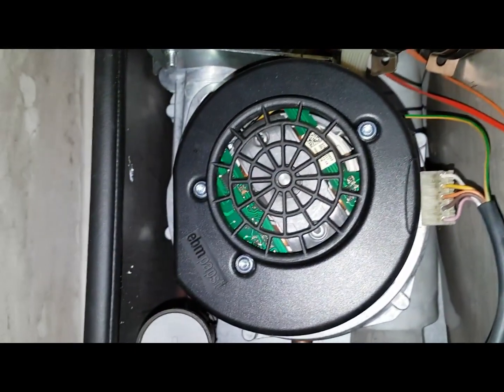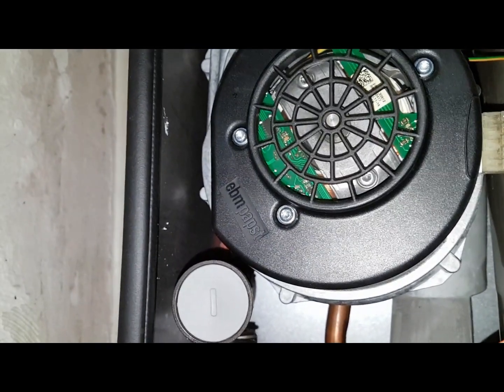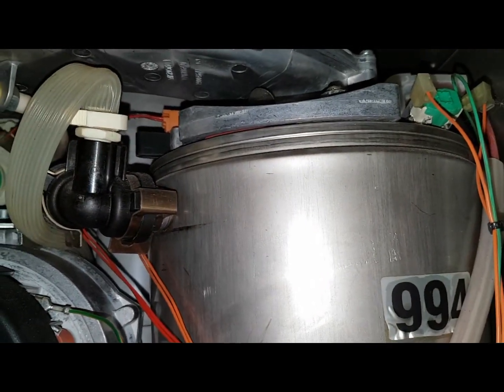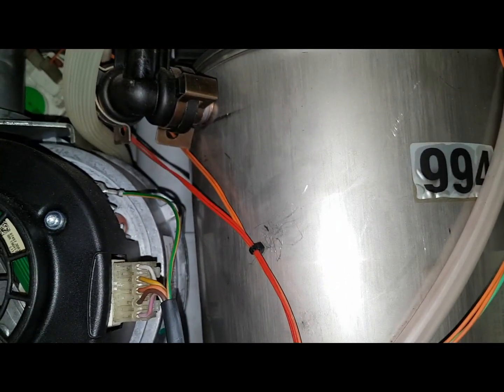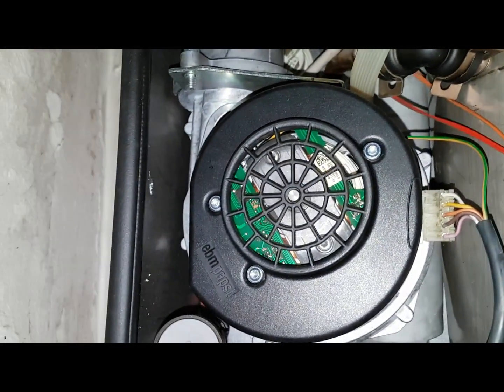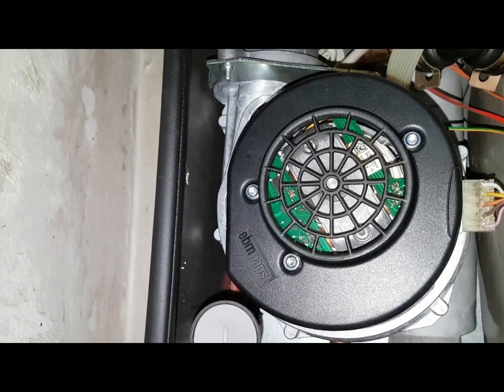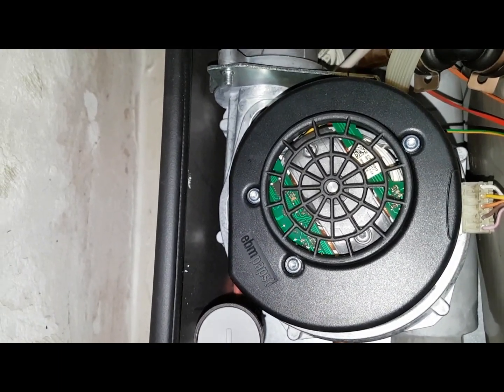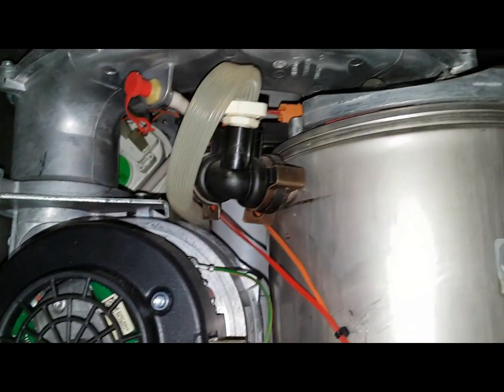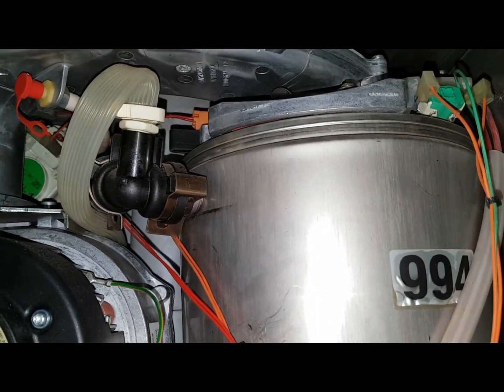So it reduces the fan speed, which reduces the gas, reduces the air, reduces the burner intensity, which reduces the heat. So when it needs more heat, the fan speed will speed up to give more gas and air and make that burner more intense.